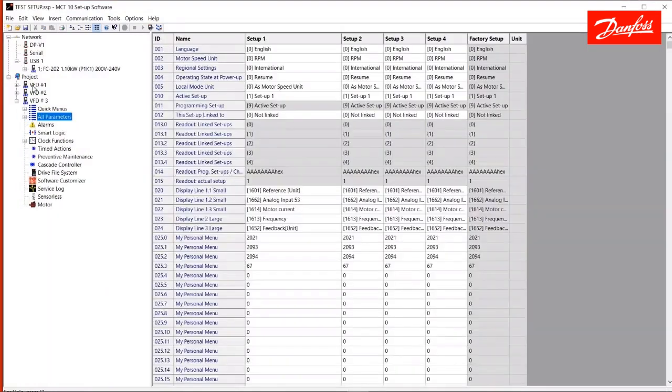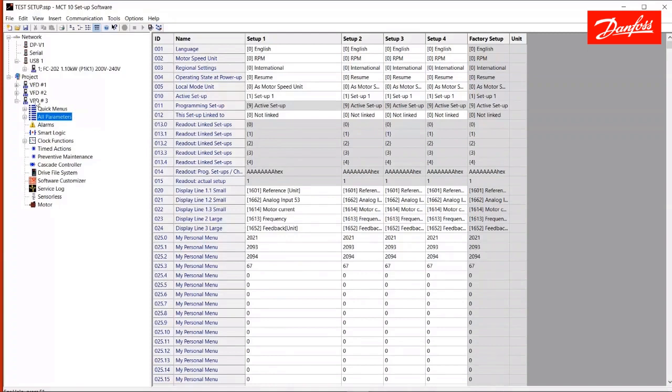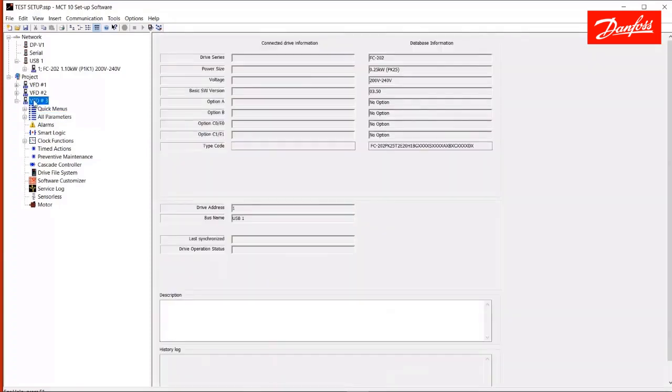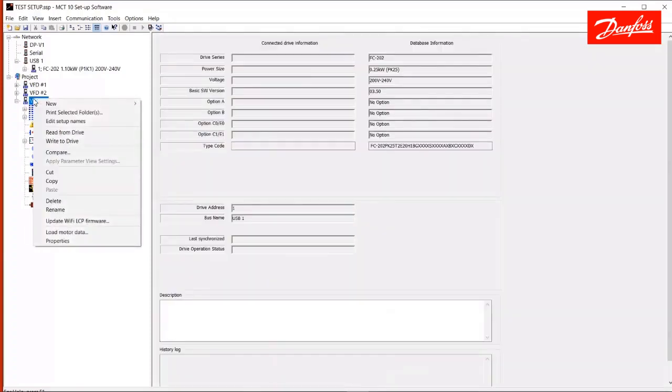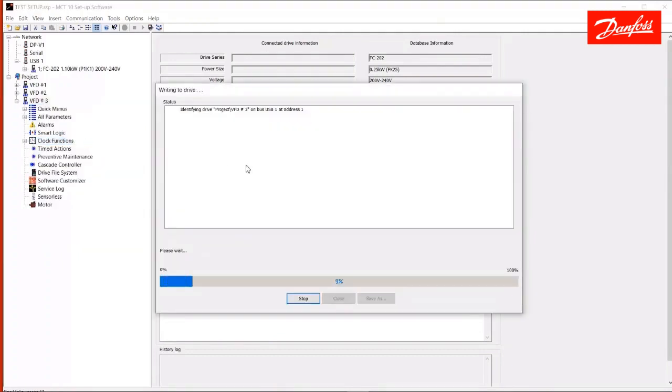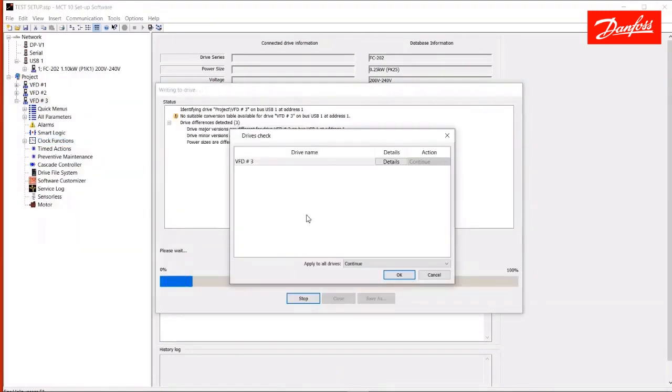Of course, you can save this project file. When you get to the field and you open that project, you would connect again to the drive of interest that you wish to write the data to. And at that point, I would right click and again select write to drive. Now, I'm going to do this here, and we're going to see what happens. This is going to give me some warnings here, first of all. It's saying that there are drive differences detected. One, the major versions may be different, and the power sizes are different.